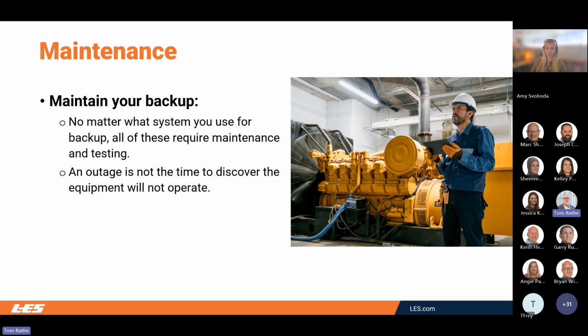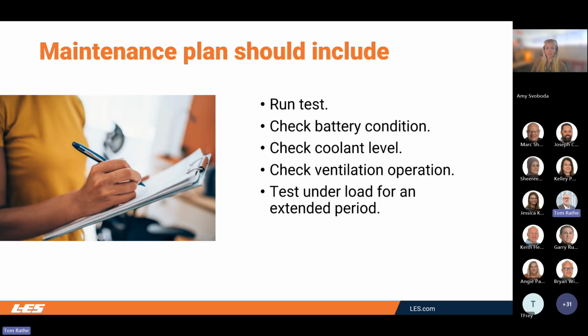Most of these installations are considered critical loads, and the customer is seeking our assistance to quickly respond to their facility and get the power back on. We're sympathetic, but it really comes down to the customer to maintain that and make sure that thing is ready to go. An outage isn't the time to discover that your backup equipment isn't going to serve you. So maintain and test is the best way to be prepared for that situation.